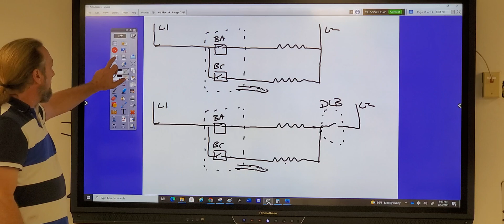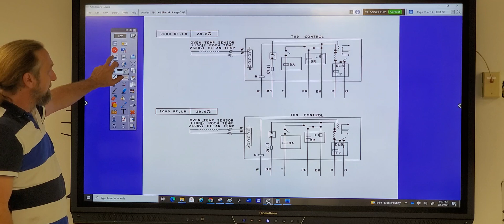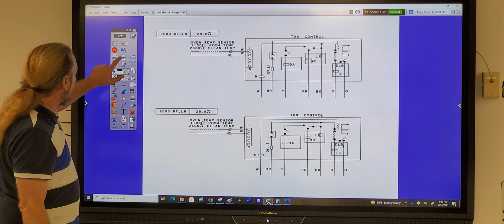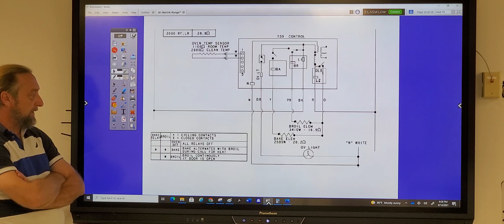Okay? So, let's go to, okay, we did these 2 circuits here. Let's go to this circuit here. So this is the corrected circuit. Now what I want you to do is pay attention to here. Bake has 2 asterisks, broil has 1 asterisk. What is that telling you there? What's that information on that chart telling you? Bake alternates with broil, the one called for heat. Bake alternates with broil when calling for heat. So the legend here says cycling contacts. I know that doesn't look like that star there, but that's what it is.